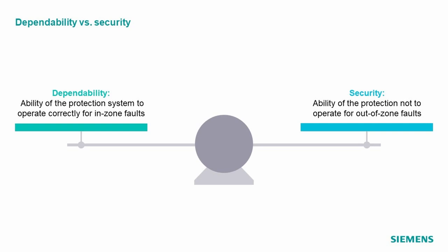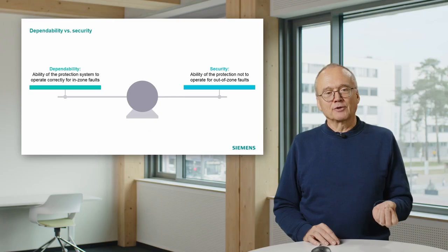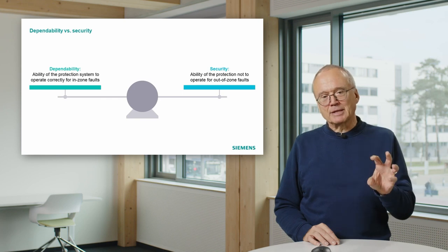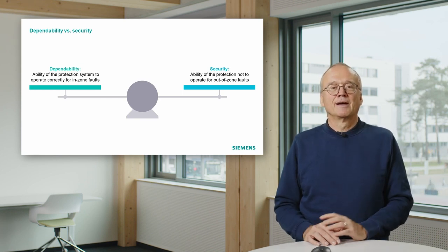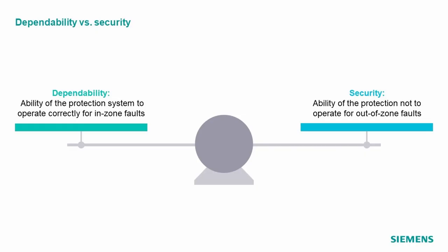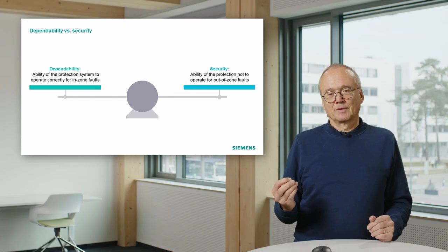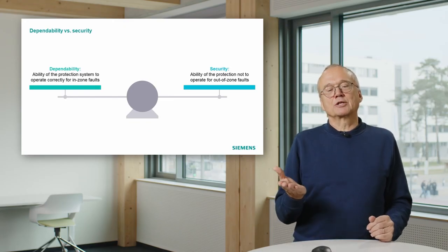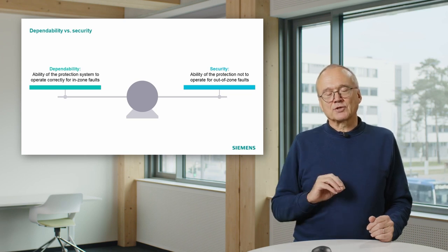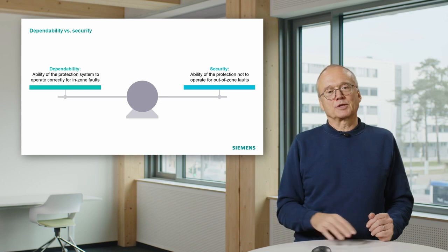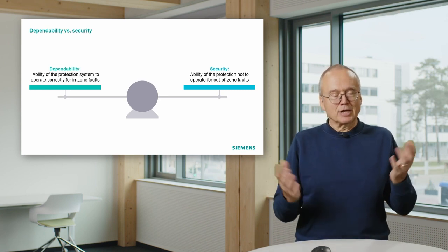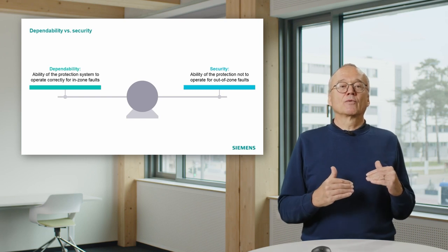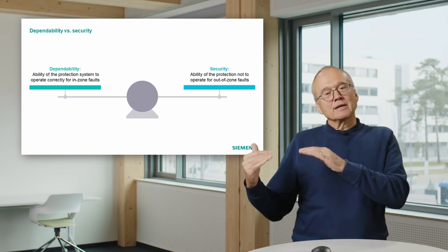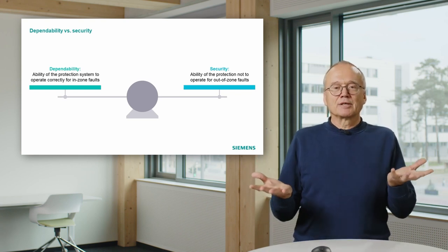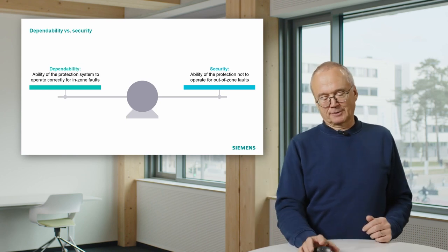Dependability addresses: can we depend on the relay that it will trip if there is a fault in the zone? That means the dependability addresses the risk of a missing trip. On the other hand, the security addresses the risk of an unwanted operation. That means if we want to increase the security of a protection scheme, we want to reduce the risk of an unwanted trip on a fault outside the protected zone. And these two issues have to be balanced. If we, for instance, increase the dependability, we may decrease the security. That means we must make up our mind what is the proper balance for that.